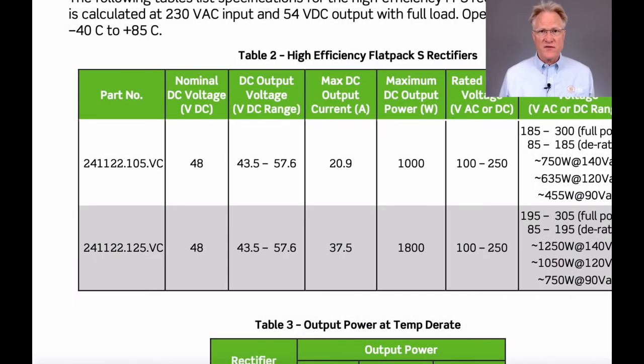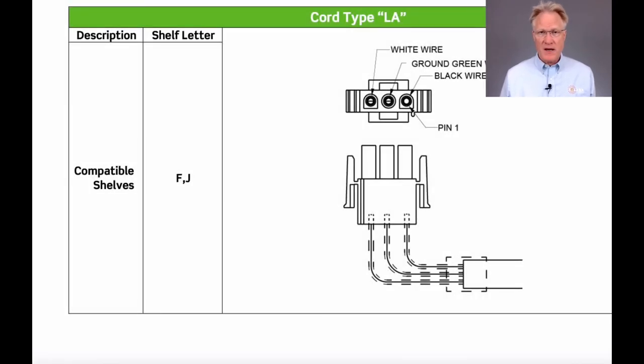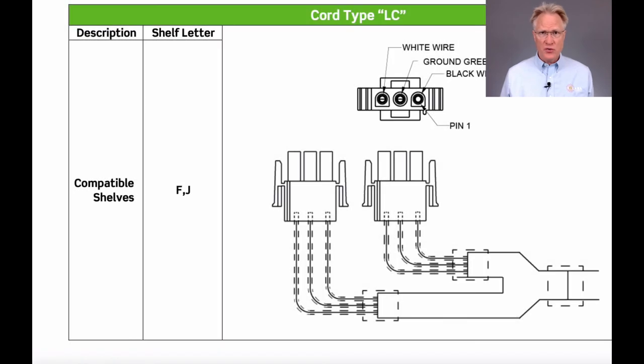The rectifiers are available in two sizes: either a 1,000-watt unit or an 1,800-watt unit. Both are derated above 45°C and work up to 85°C. The AC inputs are connectorized. Line cords are available in single connector versions to power one rectifier slot, or dual connector versions to power two rectifier slots. Both versions come in a host of lengths and are either un-terminated or can be ordered with various NEMA plugs.